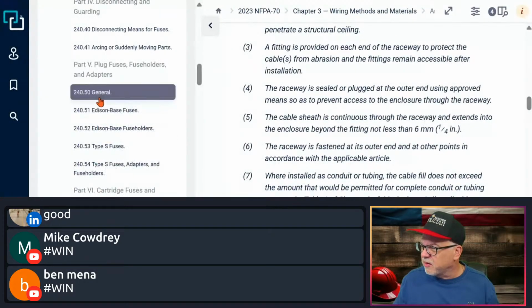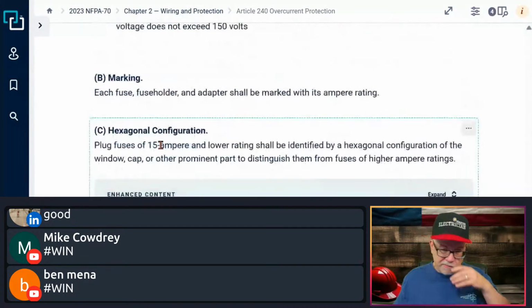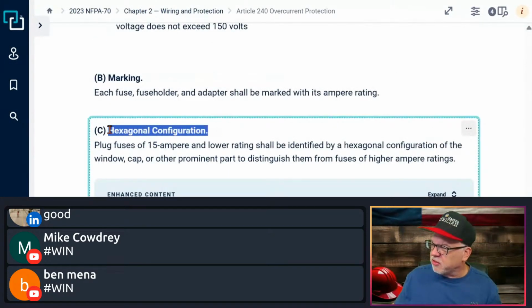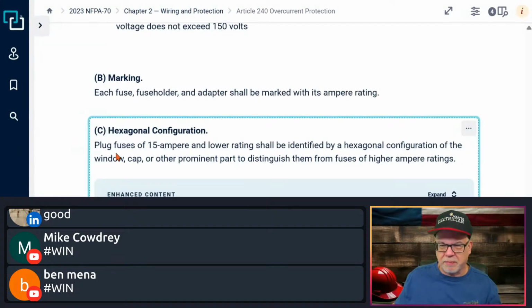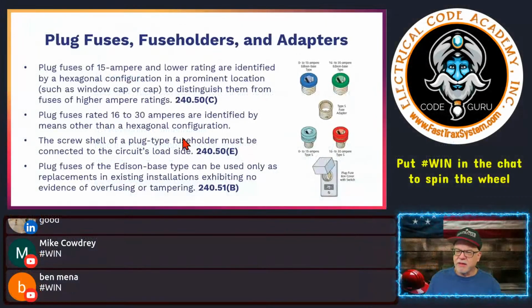But let's see here. Let's go to general. Okay, and let's go to C. There you go. Right there. Hexagonal configuration. Okay, so Edison base, we typically call these Edison base fuses. It says plug fuses of 15 ampere or lower rated shall be identified by a hexagonal configuration on the window cap or other prominent part to distinguish them from fuses with a higher amperage rating. Well, there you go. And so plug fuses rated 16 to 30 amperes are identified by means other than hexagonal configuration. Okay, so other means. Well, these look round, so maybe that's the other type of thing.